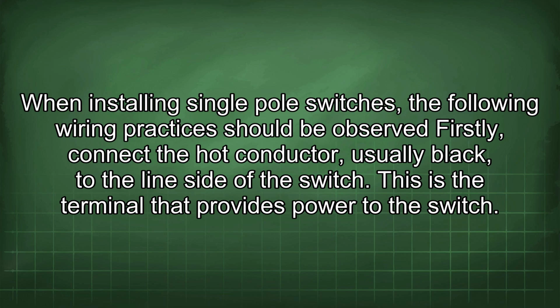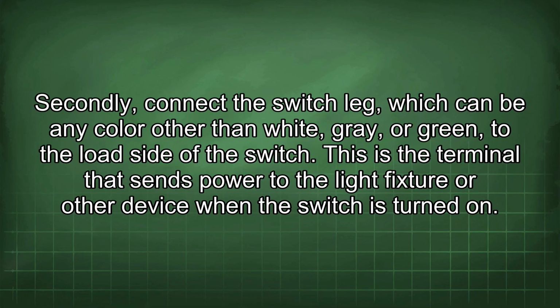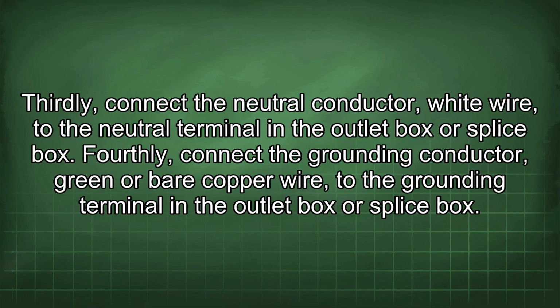When installing single-pole switches, the following wiring practices should be observed. Firstly, connect the hot conductor, usually black, to the line side of the switch. This is the terminal that provides power to the switch. Secondly, connect the switch leg, which can be any color other than white, grey, or green, to the load side of the switch. This is the terminal that sends power to the light fixture or other device when the switch is turned on. Thirdly, connect the neutral conductor, white wire, to the neutral terminal in the outlet box or splice box. Fourthly, connect the grounding conductor, green or bare copper wire, to the grounding terminal in the outlet box or splice box.